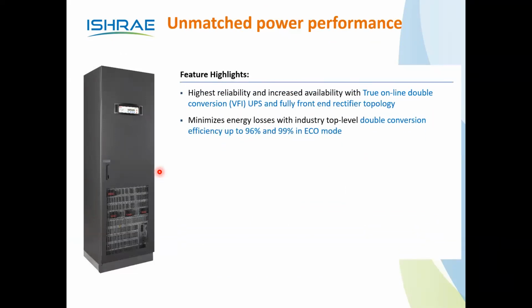And on the rectifier side, you may be aware that there are two types of rectifiers. One is the IGBT rectifier and the other is the thyristor based rectifier. The thyristor based rectifier is an old technology that comes with an efficiency of 93%, and the harmonics may be very high. Later it moved to IGBT. The IGBT rectifier is a unity input, and the harmonics have been very much subsided. And now there are additional advanced technologies, diode with IGBT. That's the main topology now, diode with IGBT, where the harmonics will be further reduced.